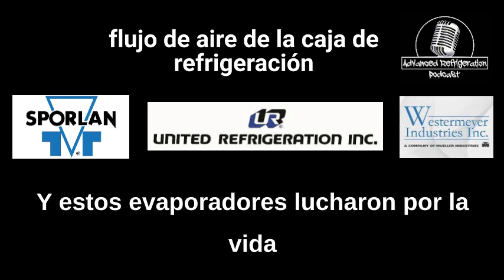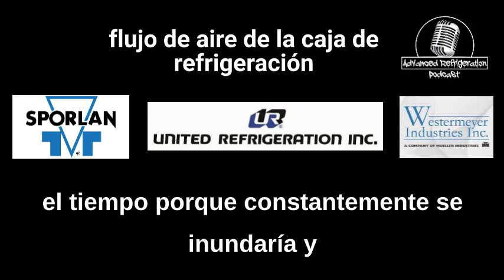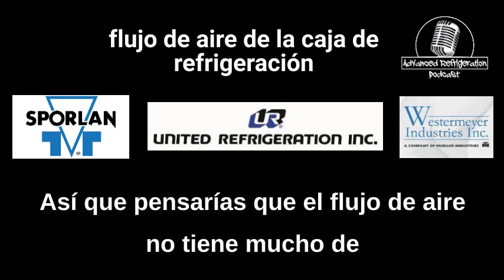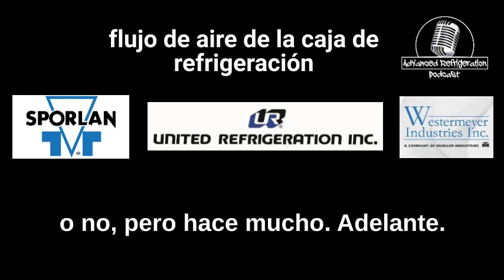And these evaporators just struggled for the life of them to maintain a good superheat all the time, because it would constantly flood and starve because of the lack of airflow. So you'd think airflow doesn't have that much of a decision on whether your stuff's messed up or not, but it does a lot.